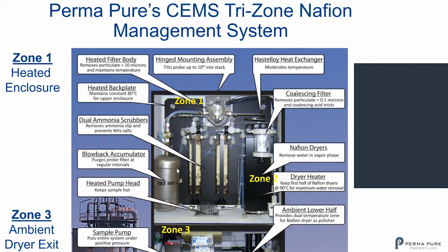A couple of other things up here in the heated section: we have our blowback accumulator. On the bottom, we have a PLC-based system. The PLC controls a couple of things. Not only does it control the temperature of all the heaters, it controls your sample pump, if you have a sample pump. It also controls the automatic drain on your coalescing filter, and the timed blowback. That's on a regular interval, where the blowback accumulator shoots out compressed air to clean the filter on the probe. That's all included in one of these systems.